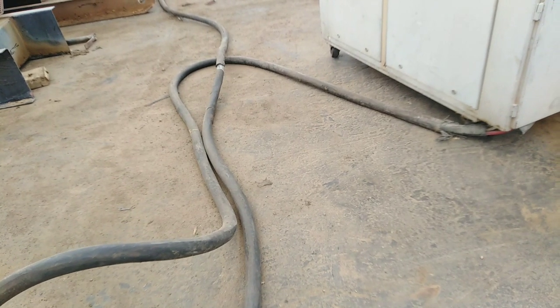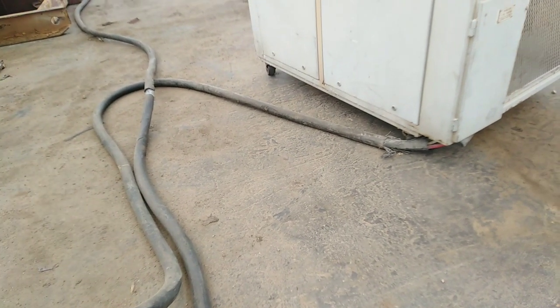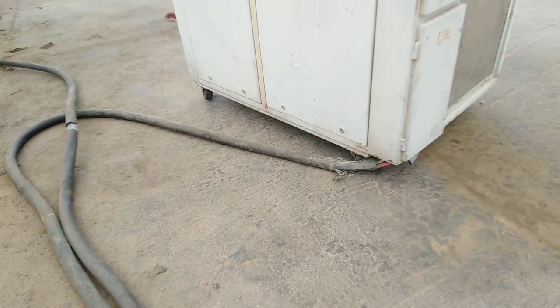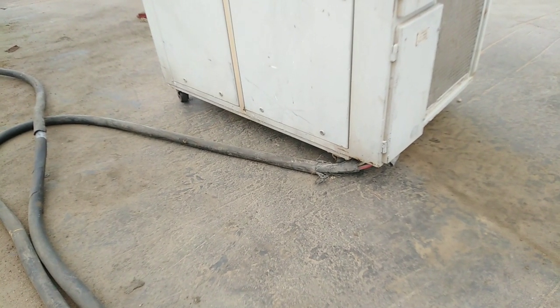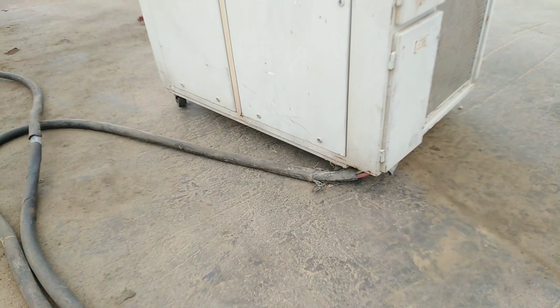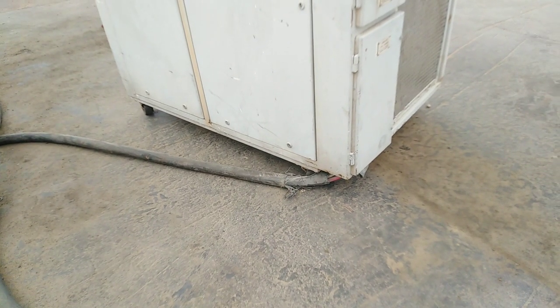When you lay out a cable, you should lay it out away from the work area, if possible. This cable in my workplace is in the way of the workers, has no warning signs, and is not set on a cable tray.